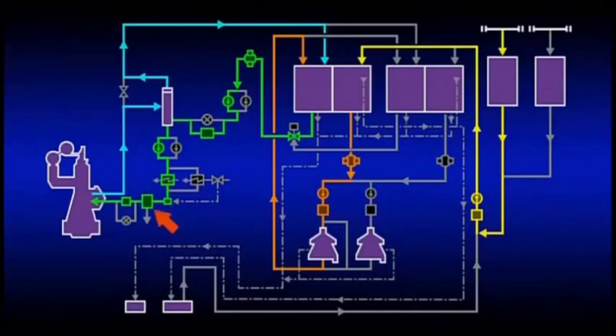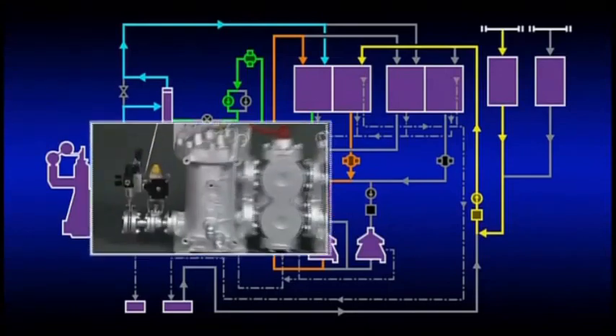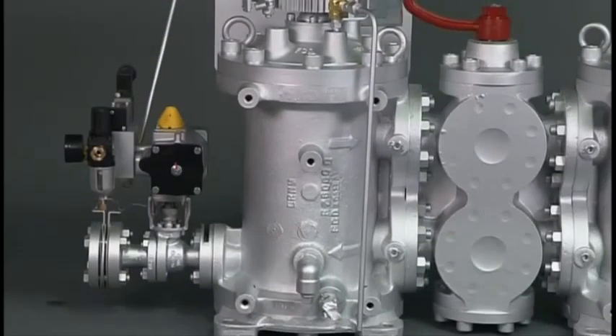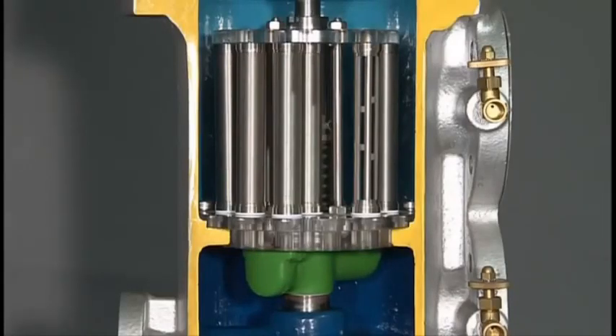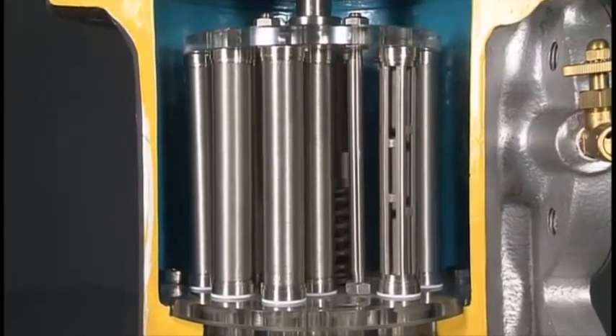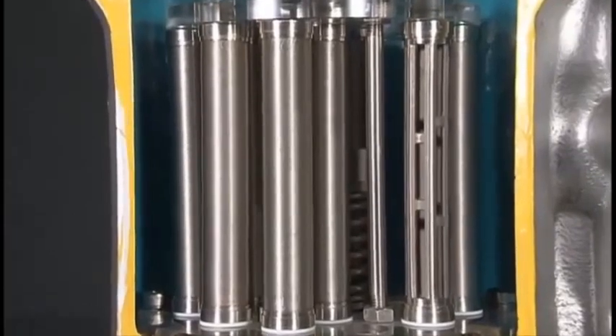Use a 10 to 50 micrometer automatic washing strainer as a secondary filter before the main engine inlet. This model is equipped with a function to perform filtration with a filtration accuracy of up to 10 micrometers while making some filtrate flow backward intermittently to automatically discharge sludge trapped by the elements.